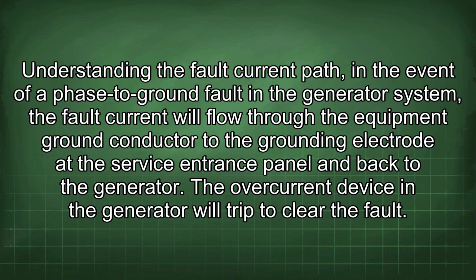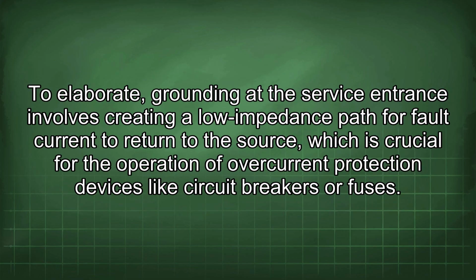Understanding the fault current path. In the event of a phase to ground fault in the generator system, the fault current will flow through the equipment ground conductor to the grounding electrode at the service entrance panel and back to the generator. The overcurrent device in the generator will trip to clear the fault. To elaborate, grounding at the service entrance involves creating a low impedance path for fault current to return to the source, which is crucial for the operation of overcurrent protection devices like circuit breakers or fuses.